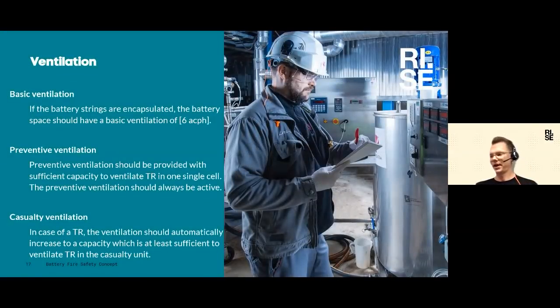Another aspect of the batteries, not related to what I showed before, is the explosion and toxic gas hazard—before it was mostly the fire hazard. For that, we also looked at a safety concept for energy storage systems, which I won't go through in too much detail, but basically you need a basic amount of ventilation in your system, while also being able to prevent or evacuate any flammable gases produced by a single cell away from potential ignition sources.